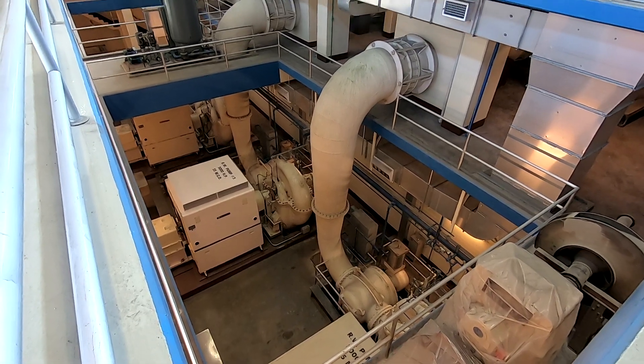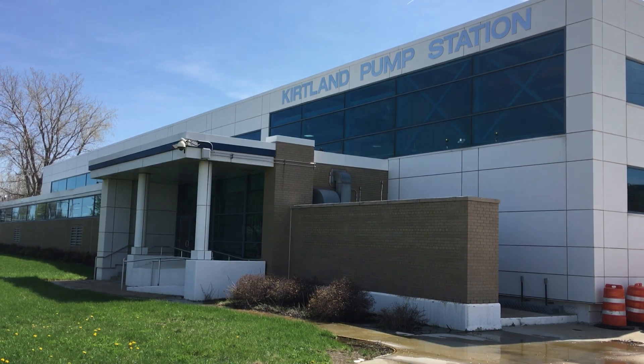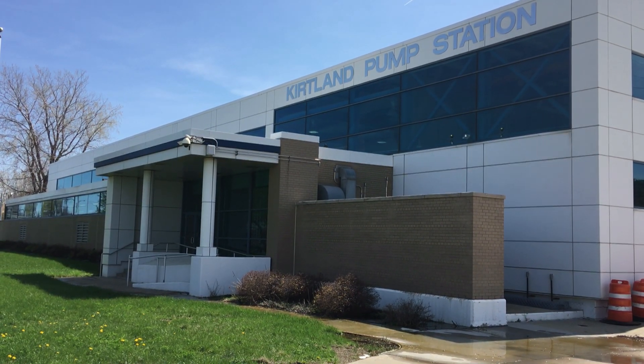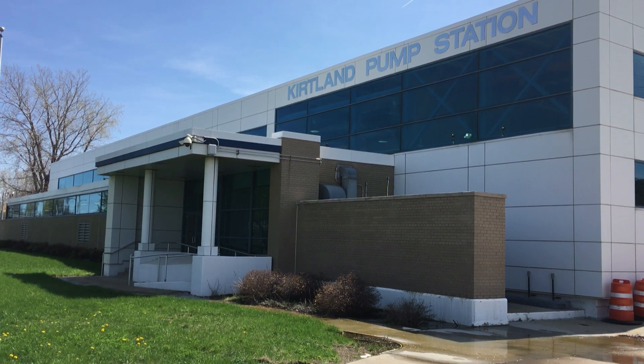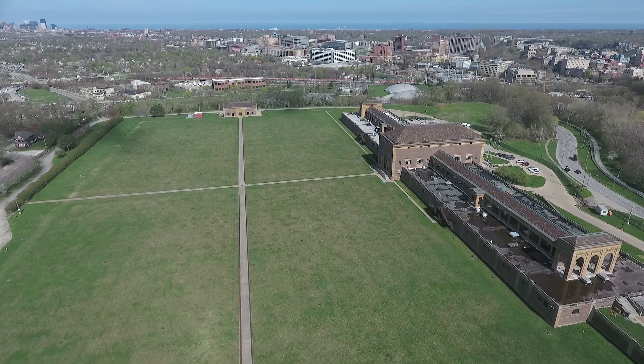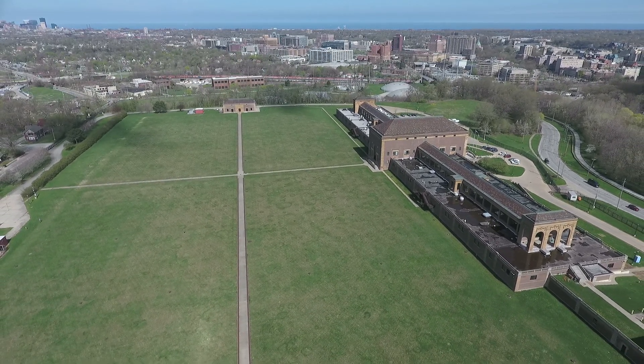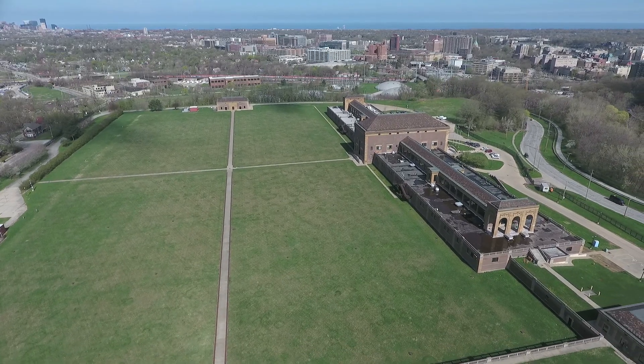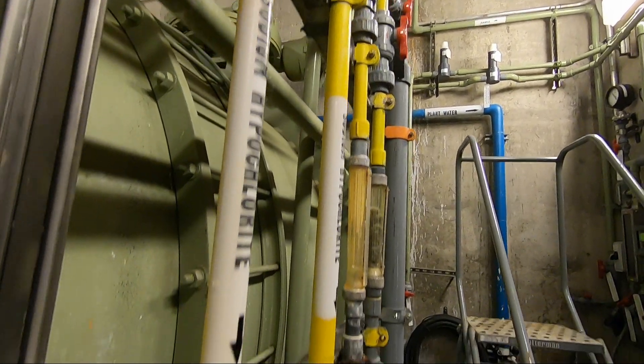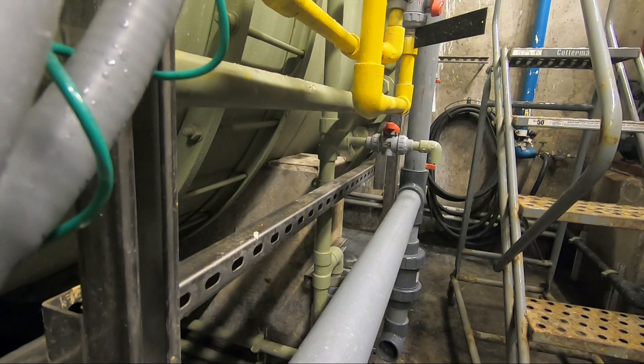Kirtland's massive pumps then move water through five miles of dedicated twin 60-inch express mains, uphill directly to the Baldwin Filtration Plant. At Baldwin, powdered activated carbon is added to help adsorb taste and odor compounds and other trace organic contaminants. Then, the coagulant aluminum sulfate is added. Alum helps suspended particles form into clumps.